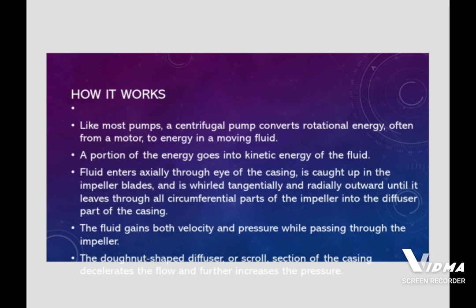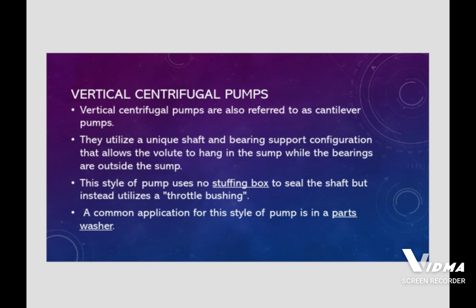Vertical centrifugal pumps are also referred to as cantilever pumps. They utilize a unique shaft and bearing configuration that allows the volute to hang in the sump while the bearings are outside the sump. This style of pump uses no stuffing box to seal the shaft, but instead utilizes a throttle bushing. A common application for this style of pump is in a parts washer.